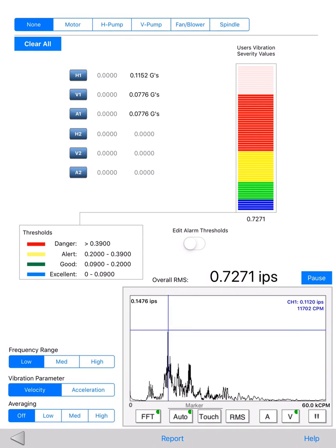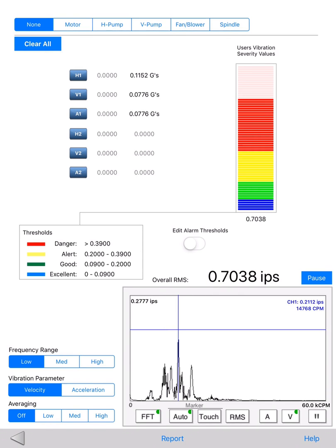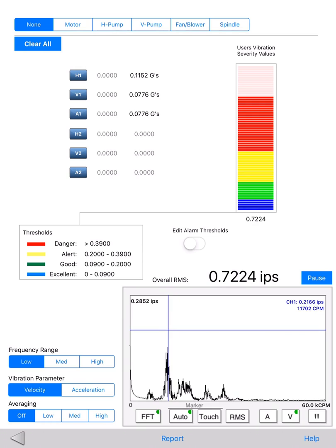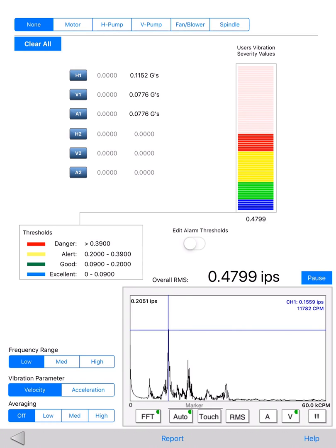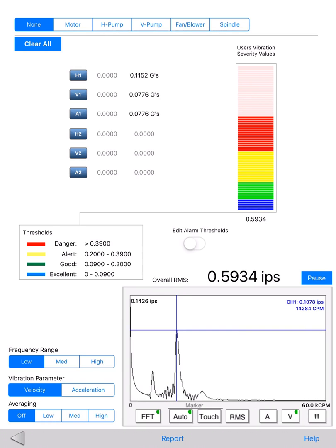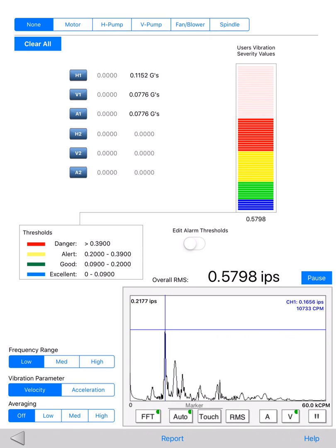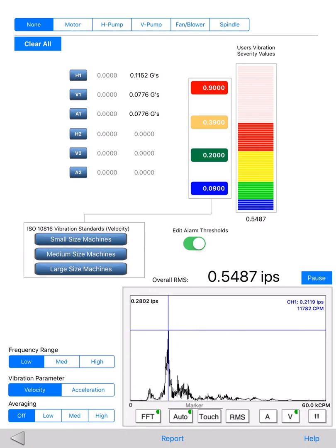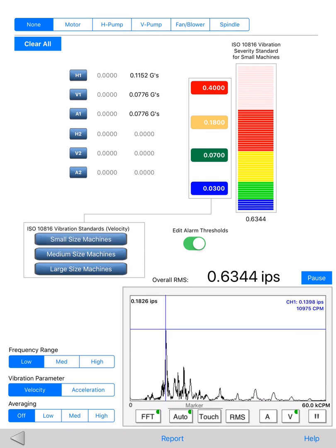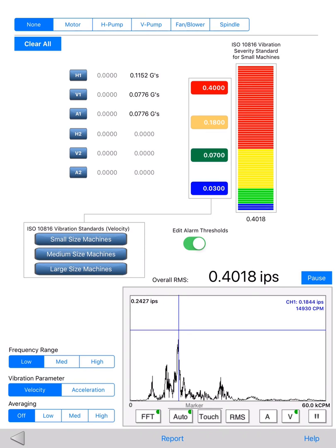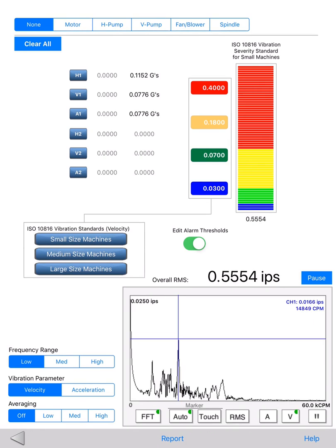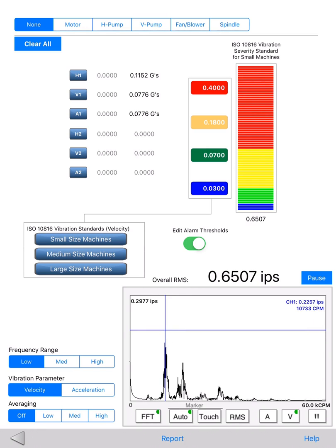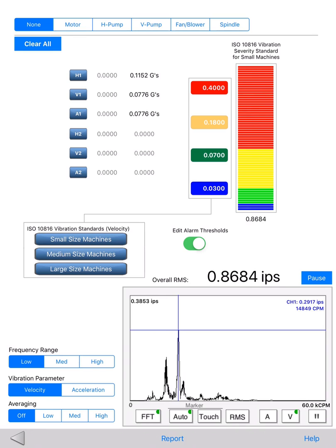On the right side of the reading capturing area, there's a vibration severity meter to help the user assess machine conditions at one glance. By default it is based on ISO 10816 vibration standards. The user only needs to toggle the edit alarm threshold switch and select a machine size group, and a set of thresholds will be automatically loaded.